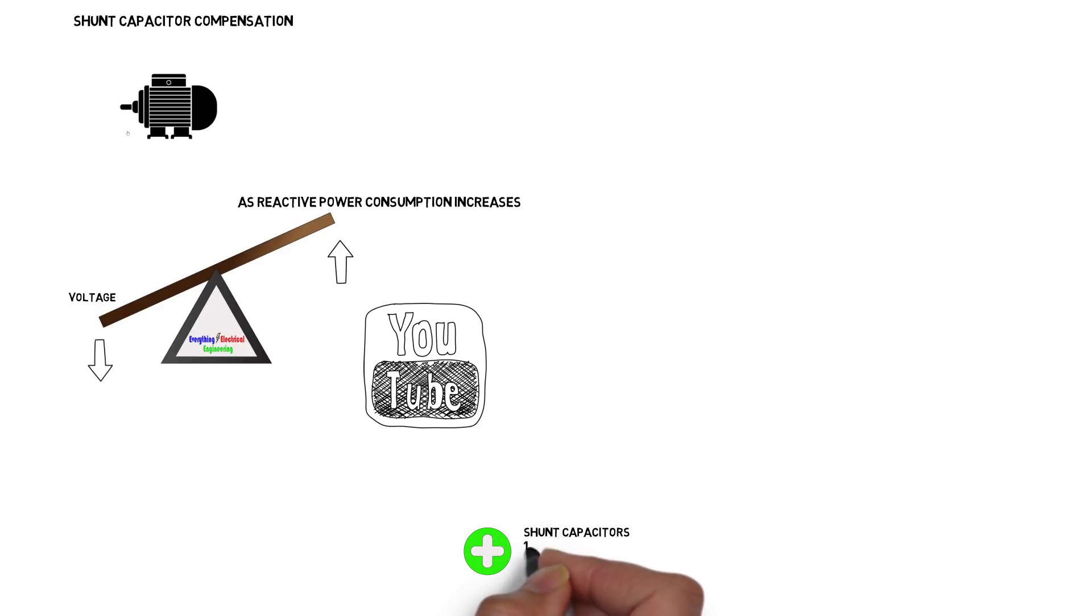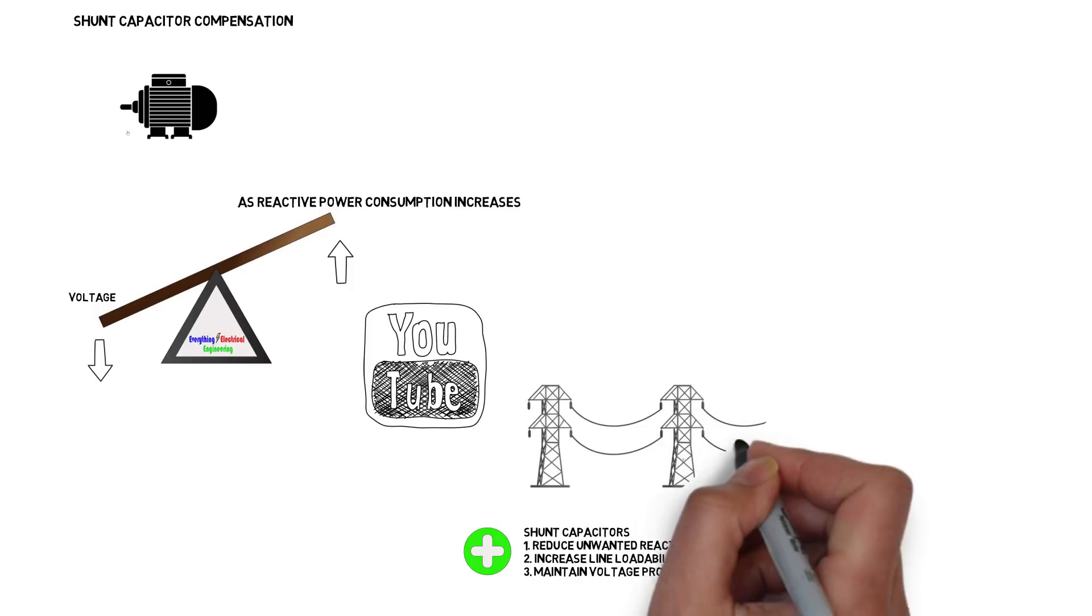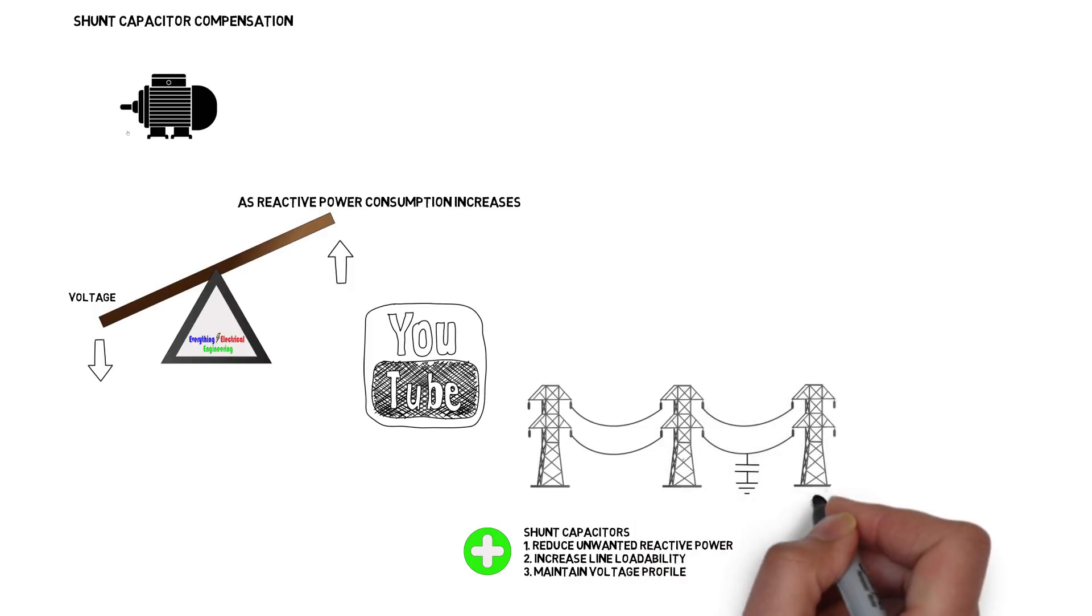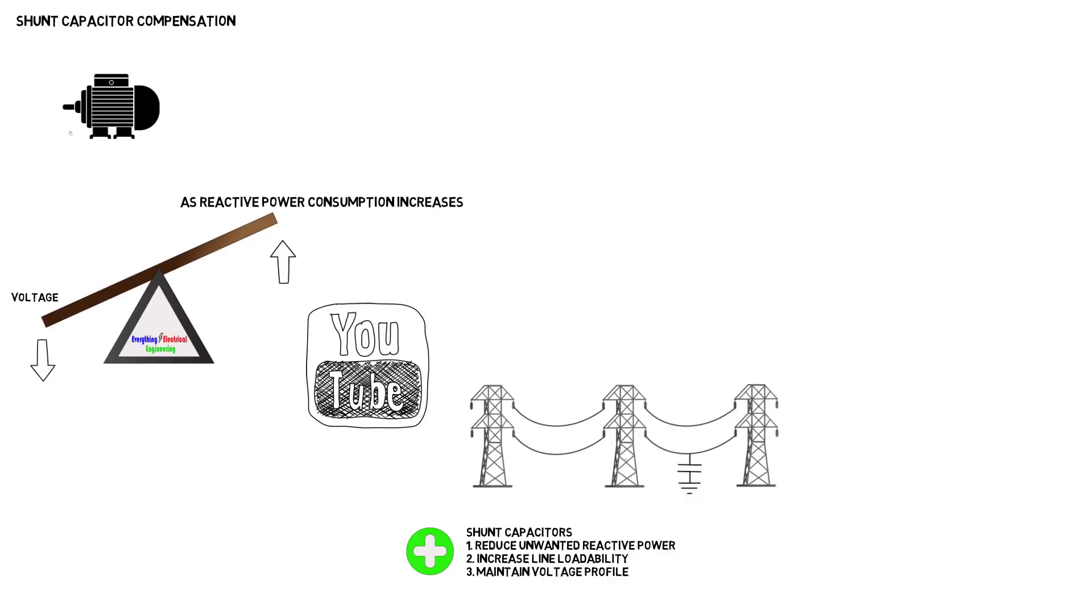Shunt capacitors provide reactive power to offset the reactive power absorbed by the loads and maintain a pre-set voltage at the receiving end terminals. Capacitors are usually connected directly to the bus or to the tertiary windings of a transformer and installed along the route to minimize the voltage drop and losses.